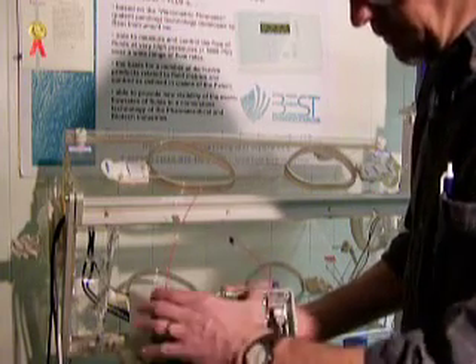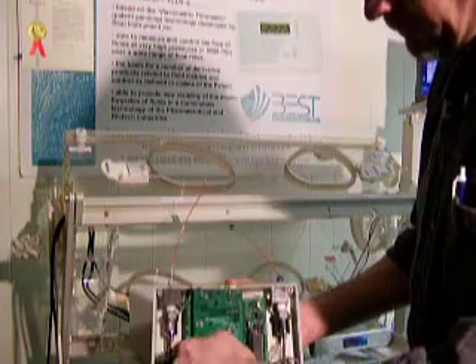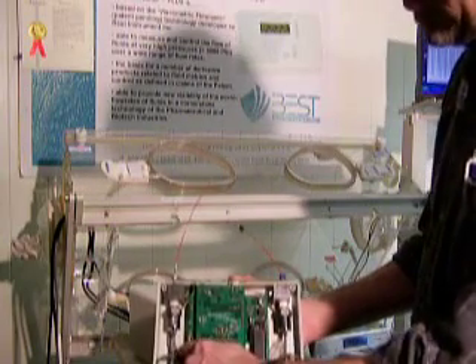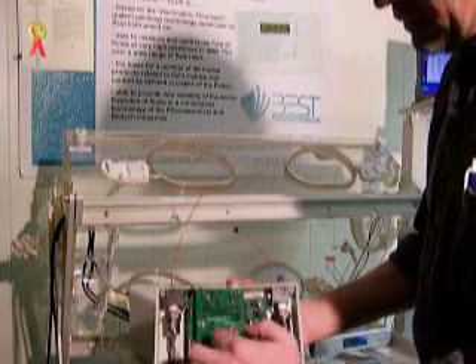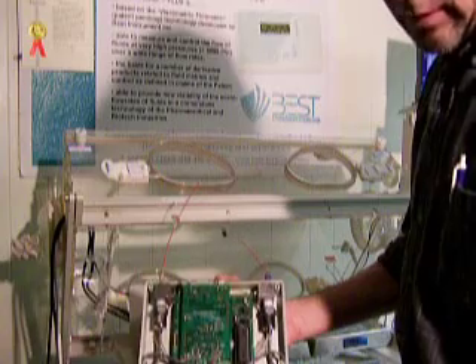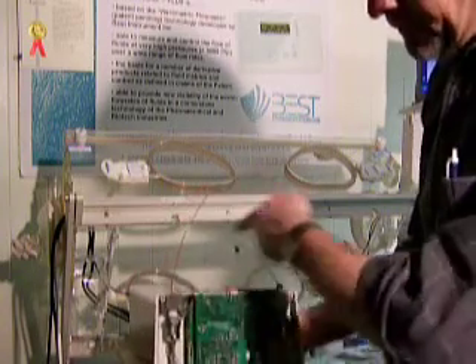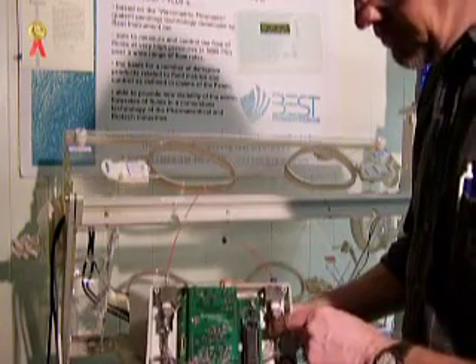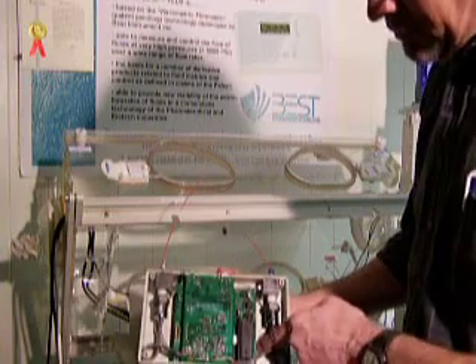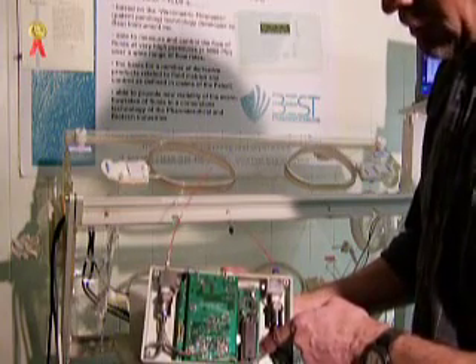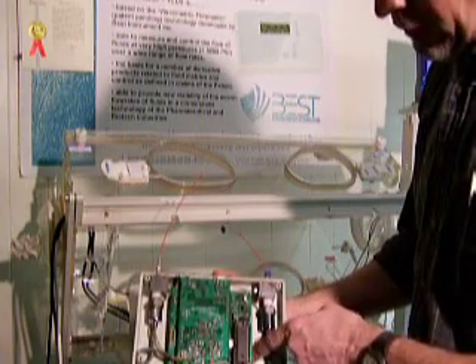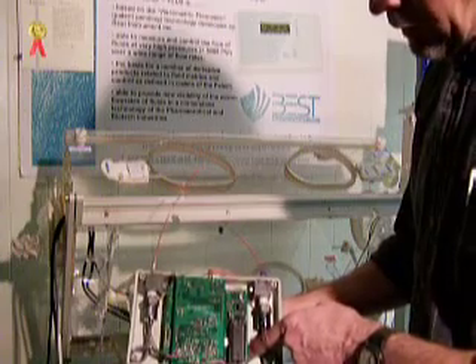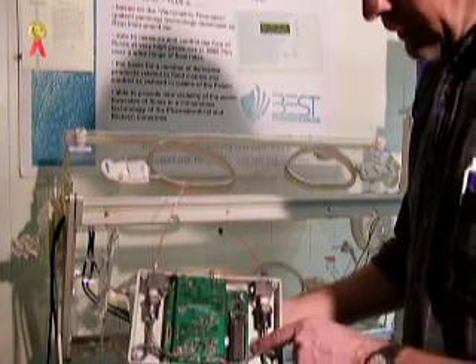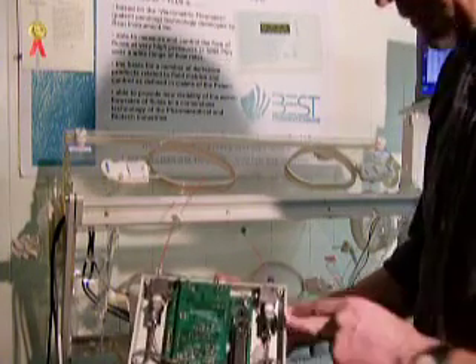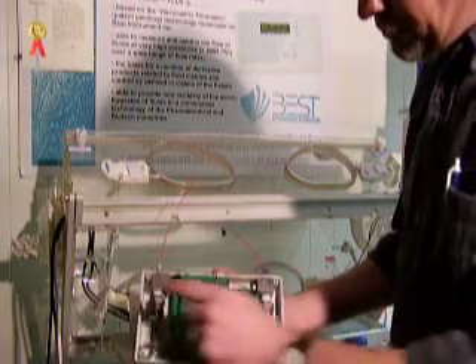The pressure difference across this loop of tubing is what gives rise to the voltages, which are digitized to then calculate flow rate. It's also essential, though, to characterize the geometry and general resistivity to flow of the tubing, and the temperature was a critical element in doing that, as well as absolute pressure, which the pressure transducers also give you.